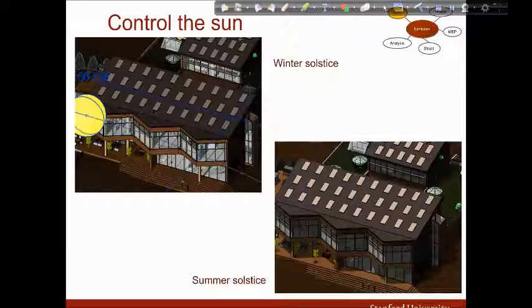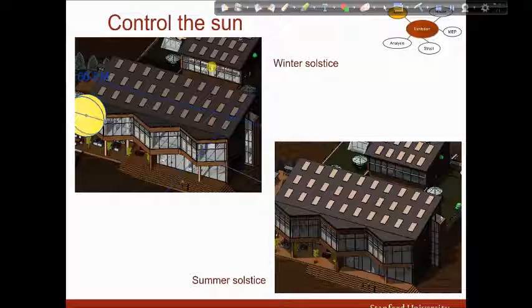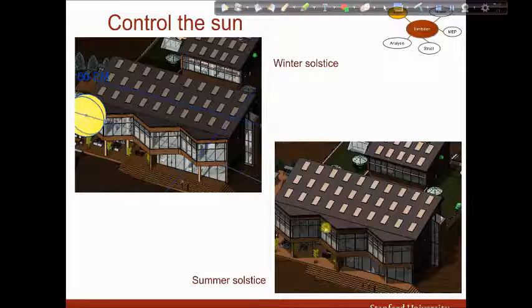My effort to control sun with overhangs is shown in these two pictures. At noon at winter solstice, I need the sun to heat my building and drive my heating loads down. This is why I allow most of it to enter the building and provide passive solar heating. However, at noon at summer solstice, I do not need heat anymore so I prevent sun from entering the building in order to reduce the cooling needs. You can see that both the front and the back side of my building are shaded.